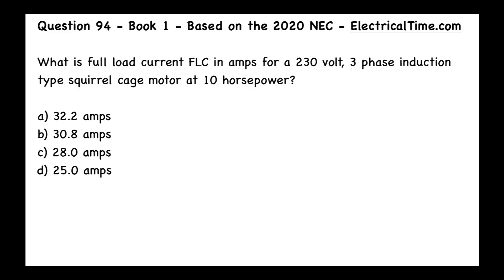The answer to this question is going to be C — 28 amps. First, we ask ourselves what article we're talking about. We see clues: FLC, full load current, and motor. That tells us we have to go to Article 430.